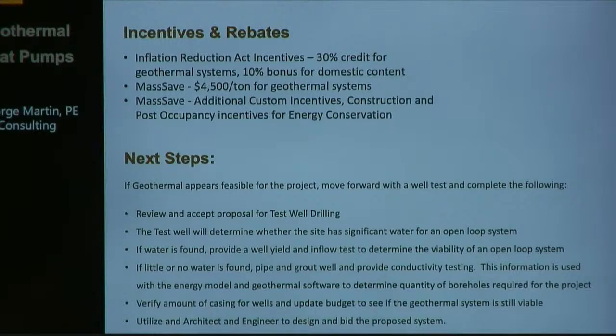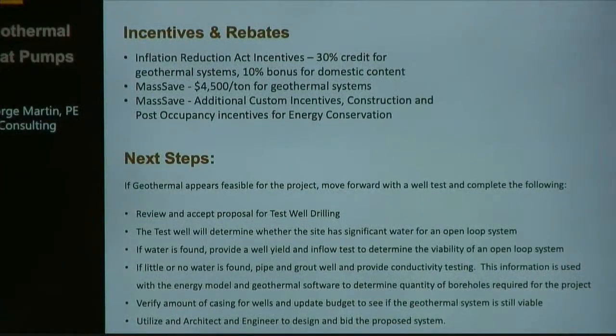Yeah. So basically, if you don't have enough boreholes, your loops will have either really high temps or really low temps, and those will trip your heat pumps. Your heat pumps are limited on the water side to, I think, like 20 to 120 degrees. They don't operate efficiently at those temperatures, obviously, so we size borehole fields, like I said, between 35 and 75, 85 degrees. Does that make sense? Yes.